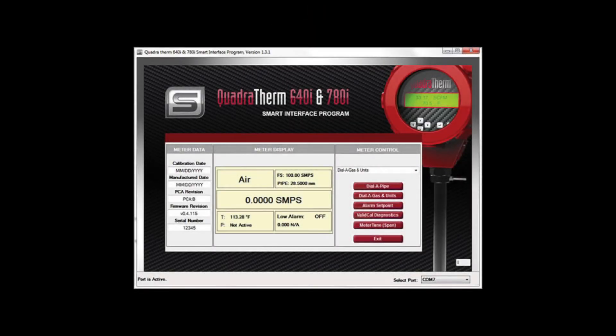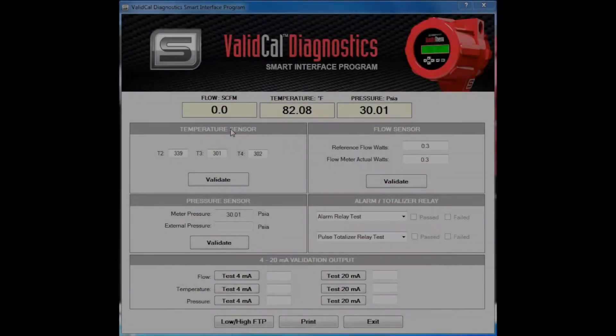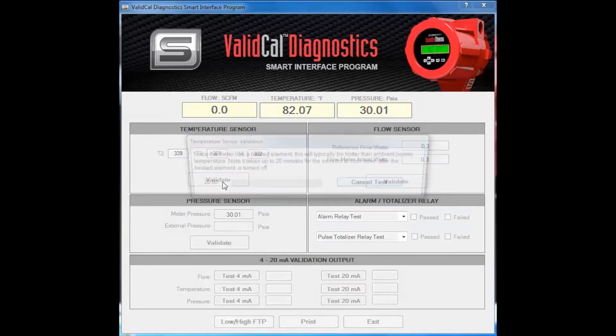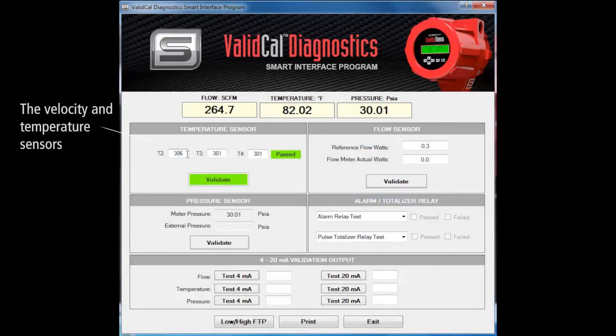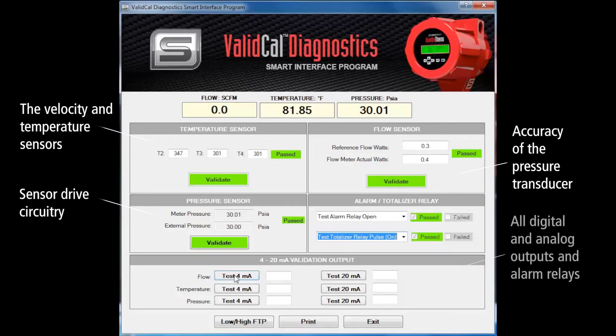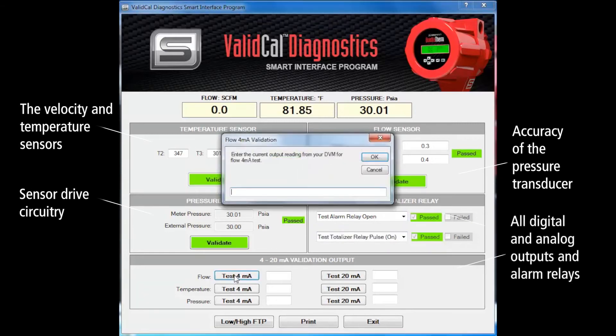Sierra offers a free in-situ calibration validation software package we call ValidCal Diagnostics. Unlike some other validation routines, Sierra's ValidCal Diagnostics program provides a complete check of all the meter's components, including the velocity and temperature sensors, sensor drive circuitry, accuracy of the pressure transducer, and all digital and analog outputs and alarm relays.